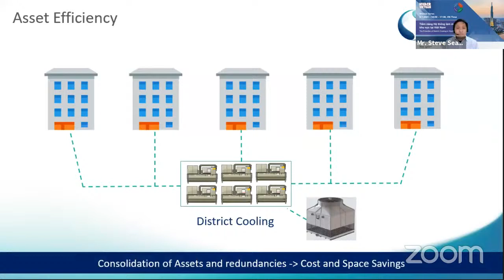This was a study conducted by one of our national agencies some time back to understand the state of chiller plants in individual buildings. The conclusion was that an average of 200% spare capacity is lying in each building. This means that for every 1 chiller operating, there are actually 2 spare chillers sitting there. So the potential for savings in terms of space and equipment is tremendous if we can integrate the plants together.